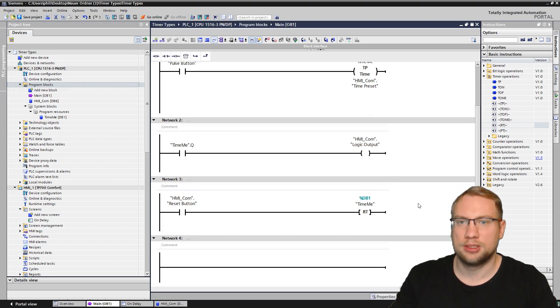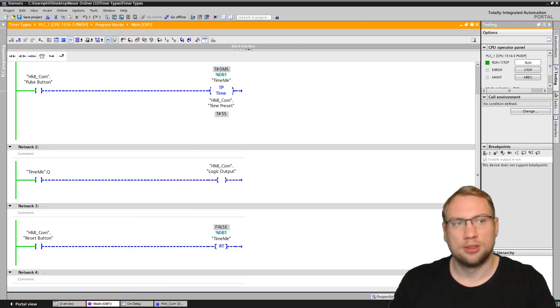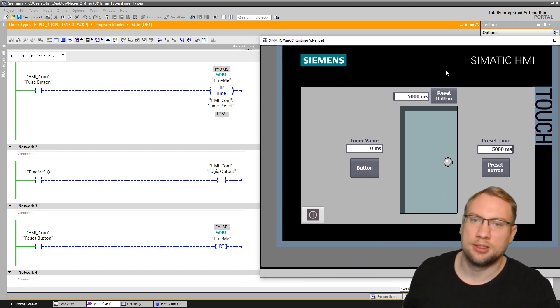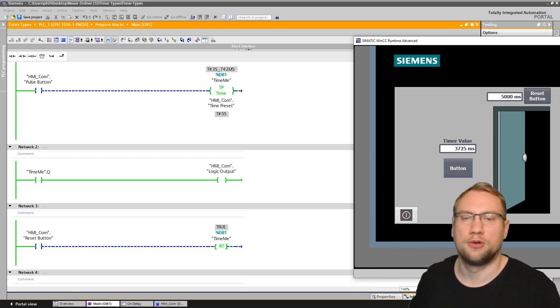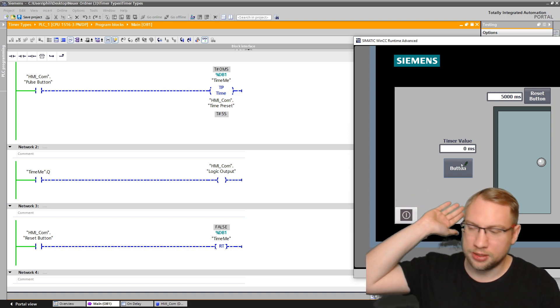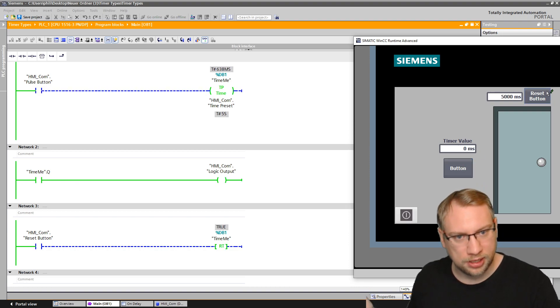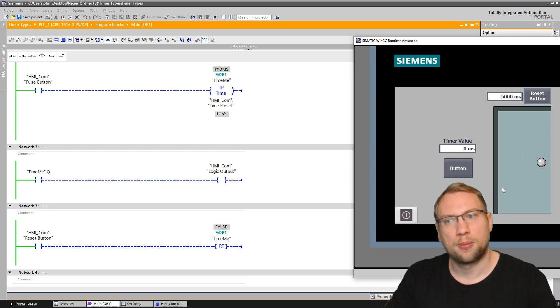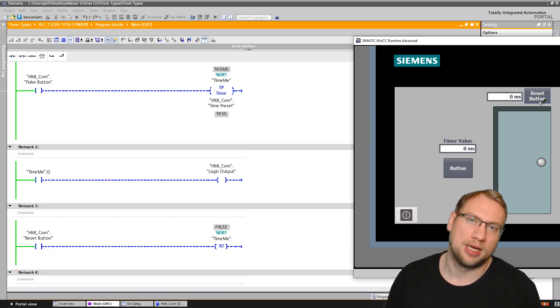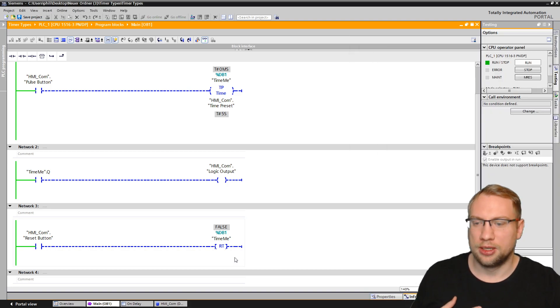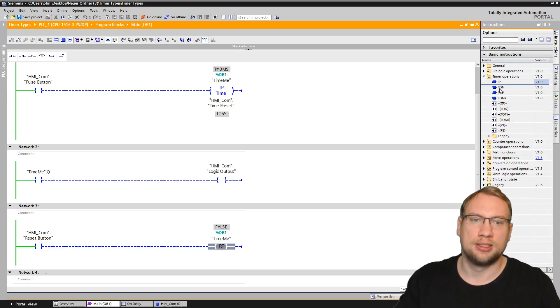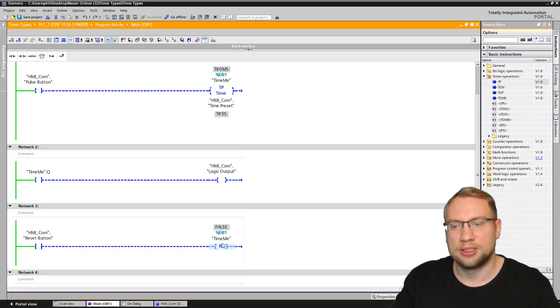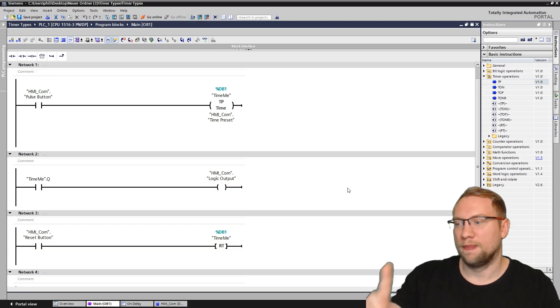I want to test this. So I press the button. The timer starts. You see the output is on. The door is open for five seconds. Now I say after a couple of time, I want to hit reset and the timer should actually reset and stop. Here we go. You see that? Works just fine. I hit the reset button. Timer goes back to zero. And it's reset. You see? That's just perfect. That's exactly what we want. It's basically a stop button for the timer. You can use that also with the standard IEC timer. You can have this instruction here also when you are just using the standard IEC timers up here. That's just a reset timer instruction. You can use that to reset any timer at any time.